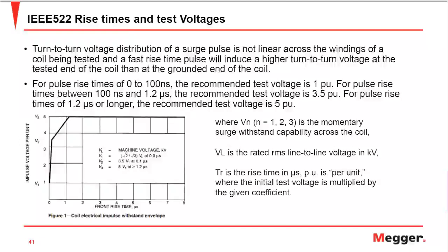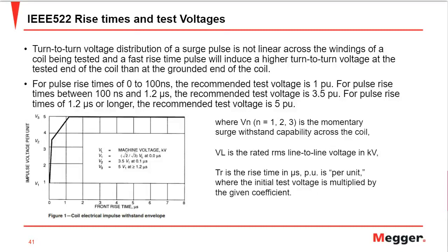And the high voltage switching networks in the Megger Baker surge testers fall under 100 nanoseconds to 1.2 microseconds, and the actual rise time of Megger Baker motor test equipment is closer to 100 nanoseconds, which complies with the IEEE 522 standard. And here is just a graphical representation of the different rise times and the different voltage levels we use for different rise times.